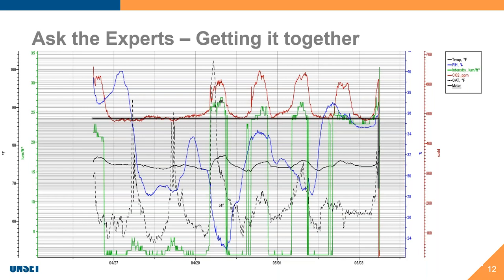On the upper right corner, we have a color-coded legend describing what you're looking at. Some a priori knowledge of the HVAC system you're monitoring is always helpful in making final determinations. This data was collected in April 2019 — pre-pandemic data. The view we're looking at is what I call a week at a glance — essentially noontime Friday to the following noon on Friday. The raw data is pulled together by the HOBO software from three different HOBO devices as simply as copying and pasting. We can always zoom in for higher resolution — we can look at one day or all seven, or get into hourly or ten-minute data, as high a resolution as desired.